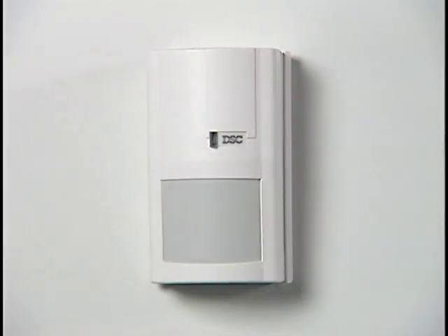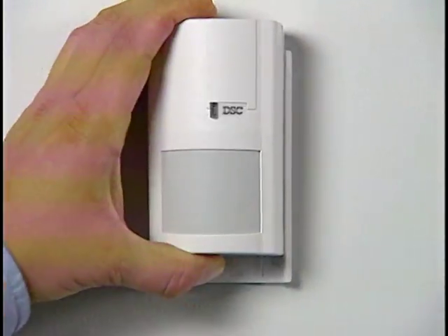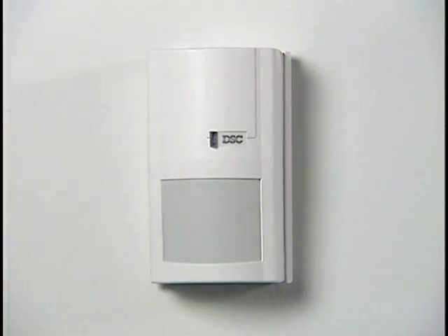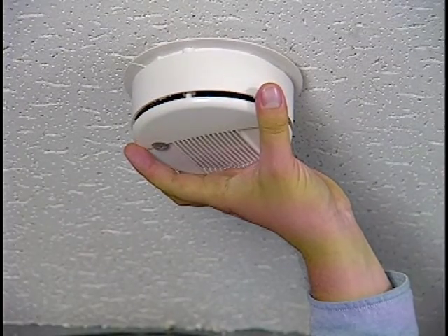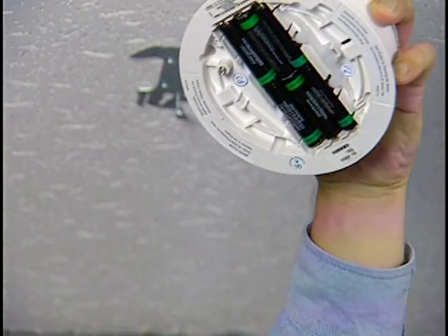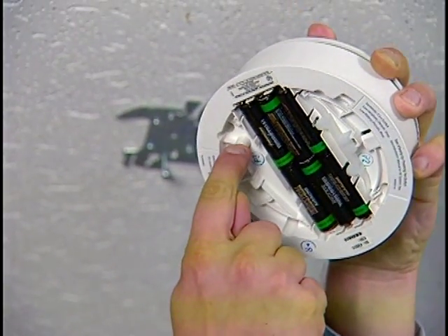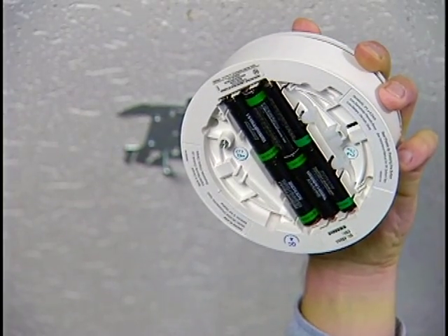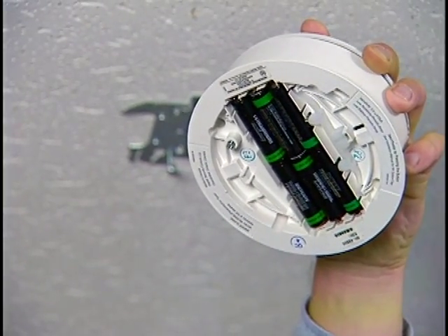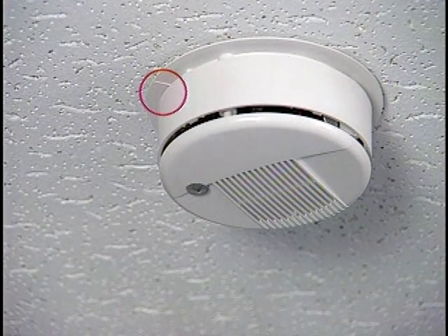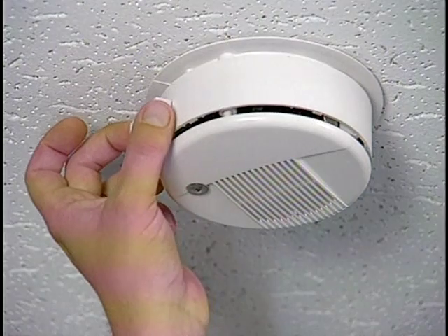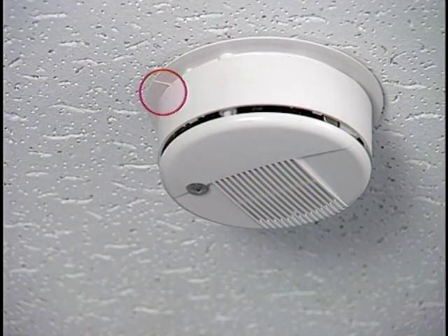When testing the WLS904 and WLS914 motion detectors, remove the backplate to create a tamper, then replace the backplate to create a tamper restoral. There are 2 ways to test the WLS906 smoke detector. The first is to remove the detector from the mounting bracket, wait 5 seconds, then replace the mounting bracket to create a tamper and tamper restoral. Or, place a magnet near the notch in the outside edge of the detector to trigger the built-in reed switch to put the smoke detector into alarm.